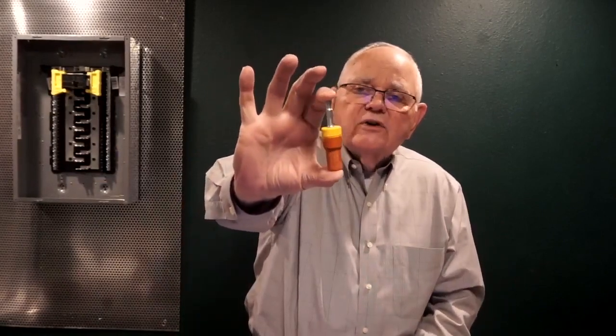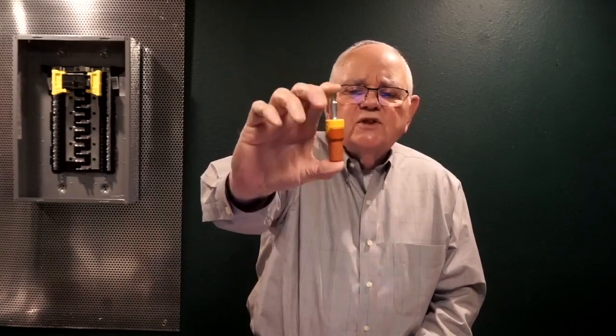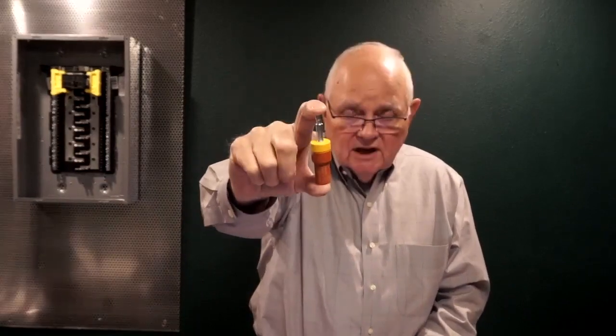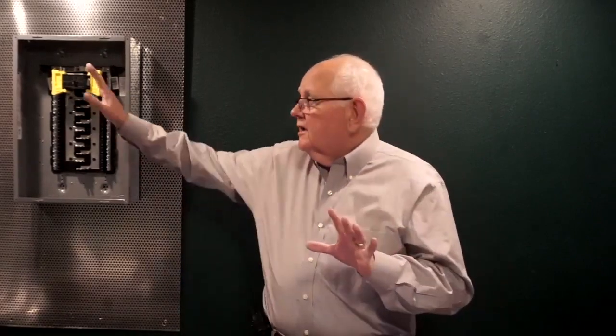Now, we talked about this insulated bit holder, and we said it was rated for 1,000 volts, and it meets the IEC standards for electric shock protection. So that's a good thing. 70E also provides us with shock boundaries. So to clear things up, we said just a minute ago, this is a barrier. It prevents inadvertent contact with live energized parts. I can set up a physical barricade that people can't cross to prevent them from getting too close and injuring themselves on whatever it is I'm working on.